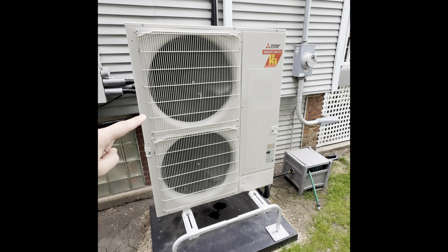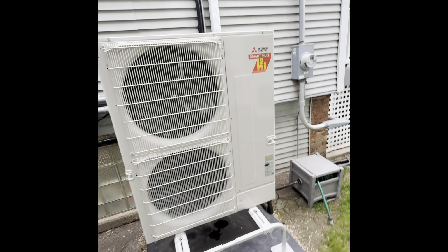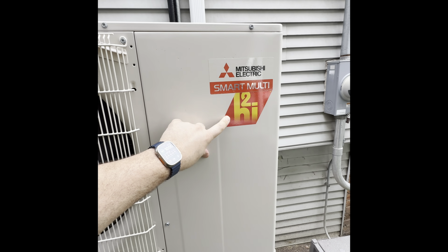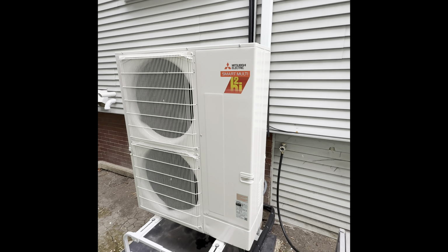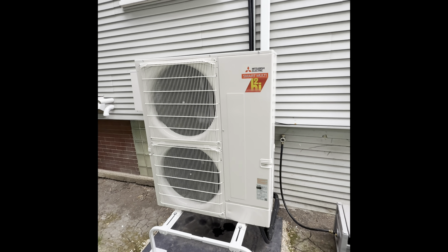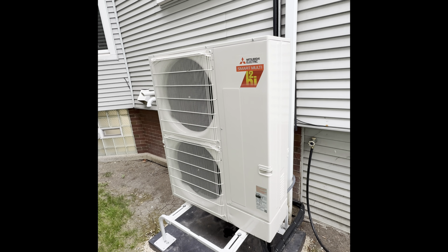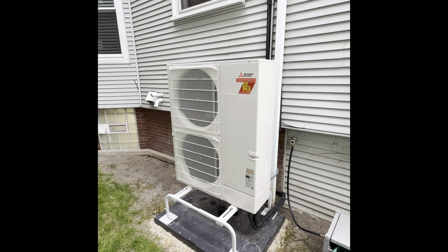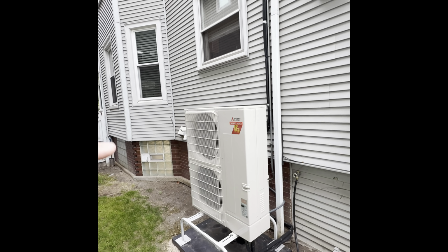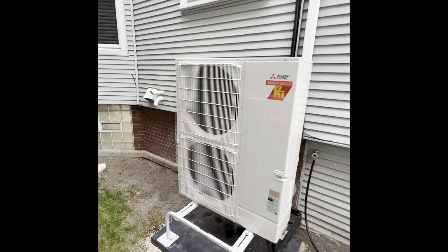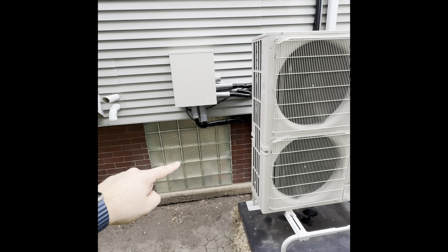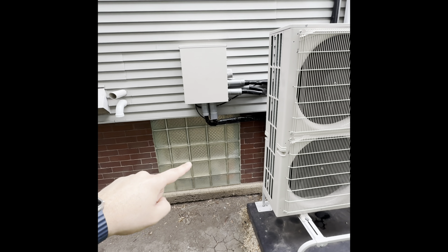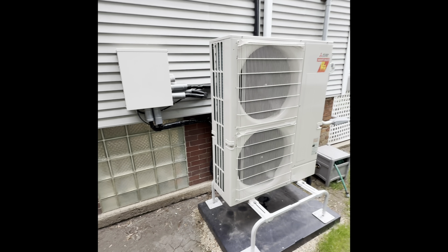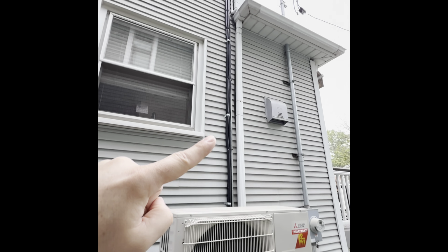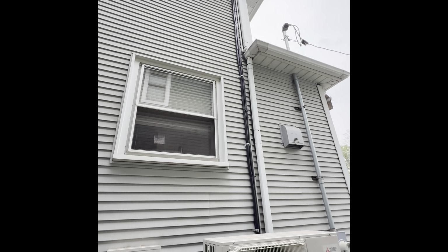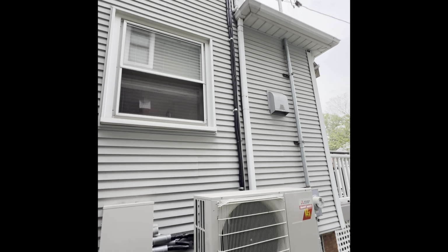Being a heat pump, this unit is also going to be doing a lot of the heating of this building. Mitsubishi calls it Hyper-Heat, or H2i. That is their definition of a cold climate heat pump, which means you can make very efficient heating down to minus 13 degrees outdoor temperatures. For this setup, as we mentioned, we have two zones. Down here in the basement, we're going to take a look soon, we have a gas furnace with a Mitsubishi dual fuel coil. It's the Intelli-Heat system. And then upstairs, we've got a line going up there. We have an air handler for all-electric heat with backup heating.